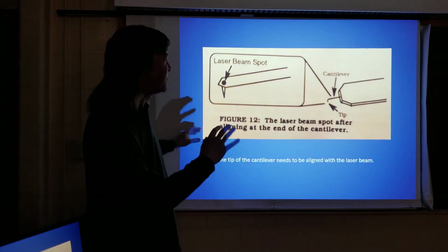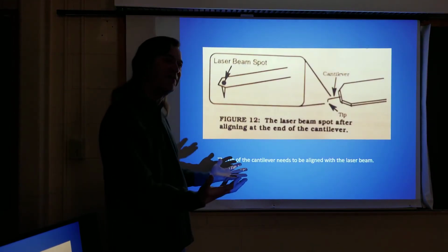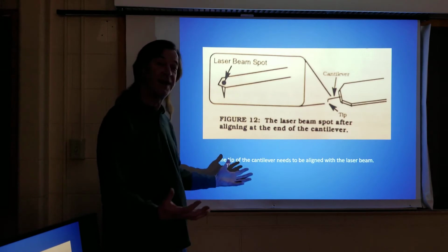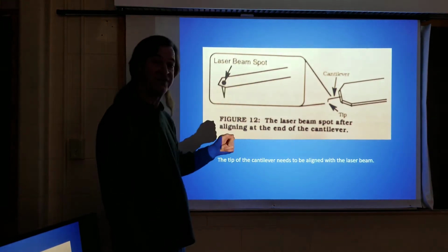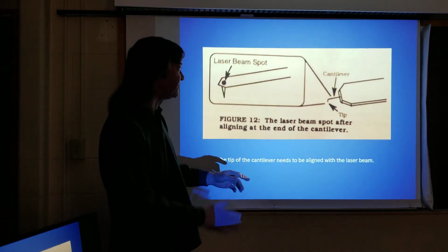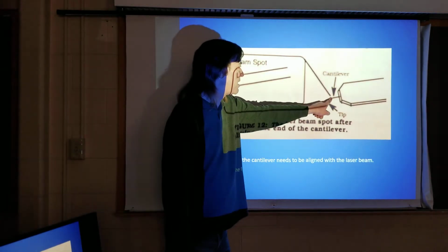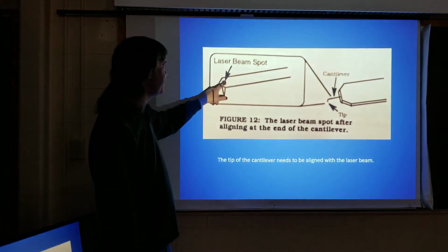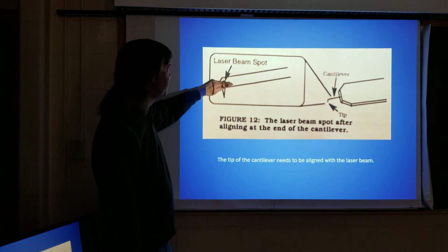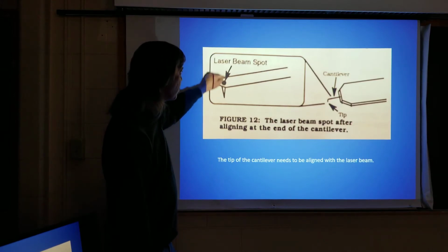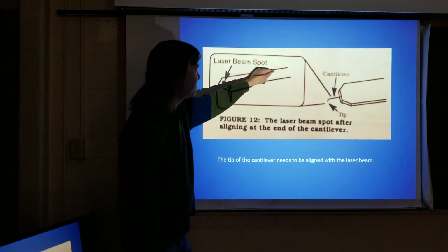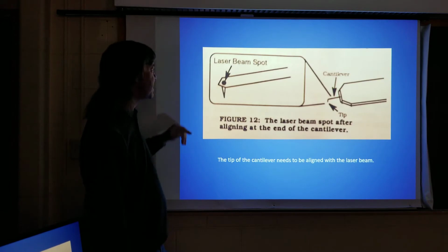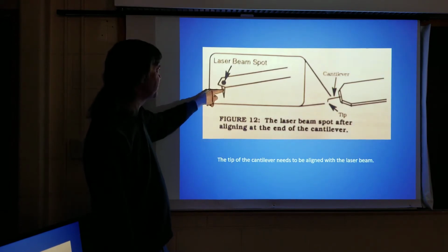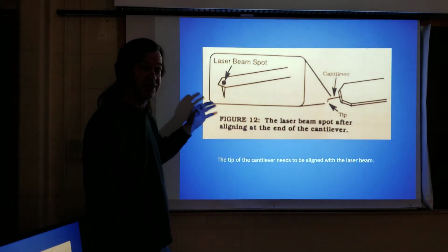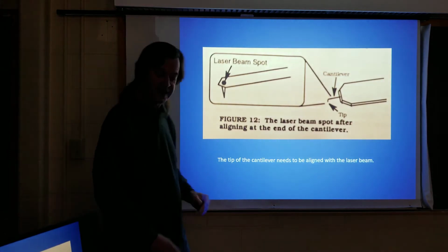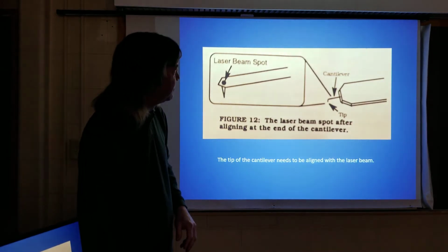It's kind of blurry, I realize, but before we can even run it, we've got this laser, it's fixed. We've got to move this cantilever so the laser hits at the very tip. You want to be as close to the tip as possible because as this moves up or down, it's going to have more movement than here and here. You get the most movement at the very end. You want to put it pretty much right over the actual tip to get your best realistic view of the sample.